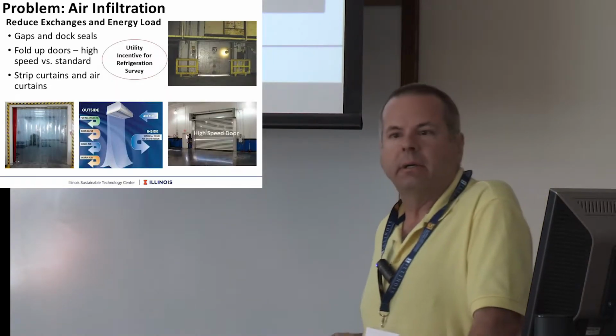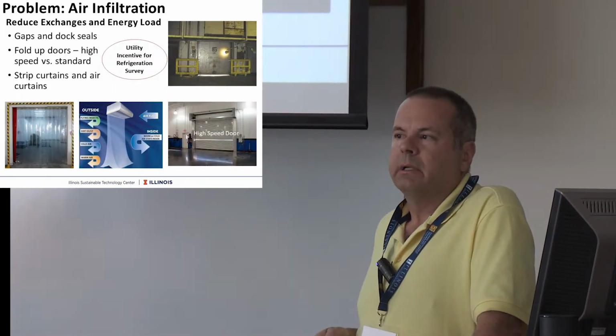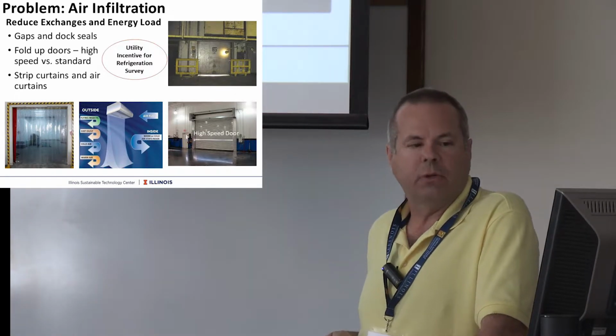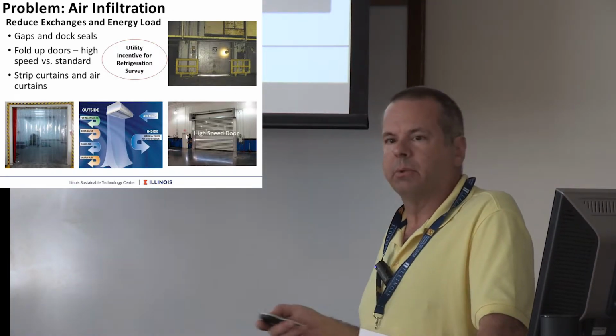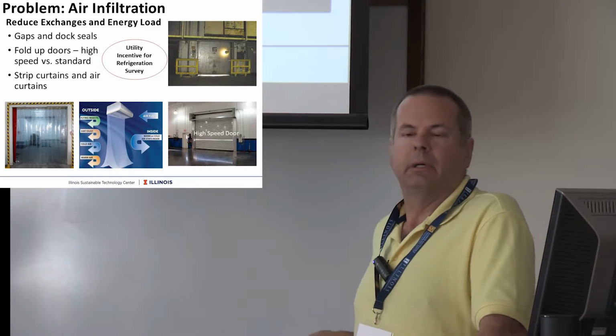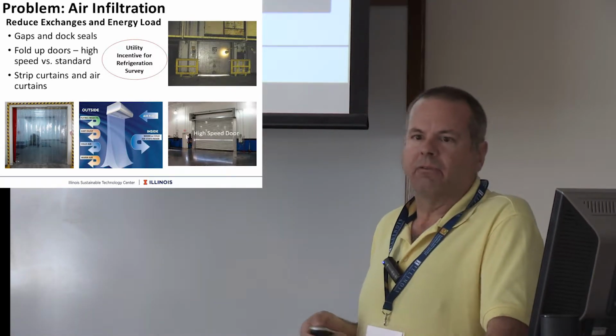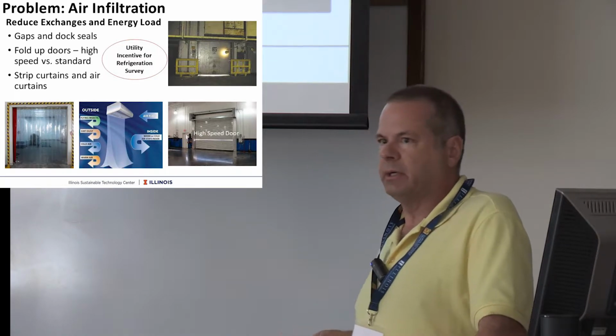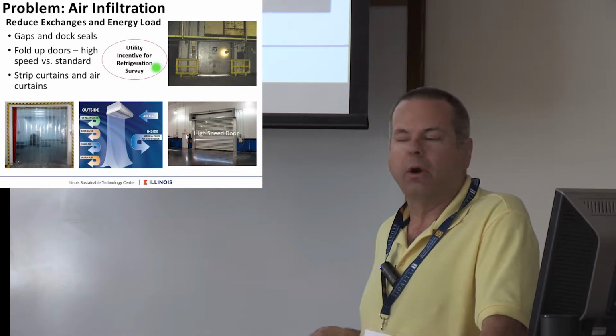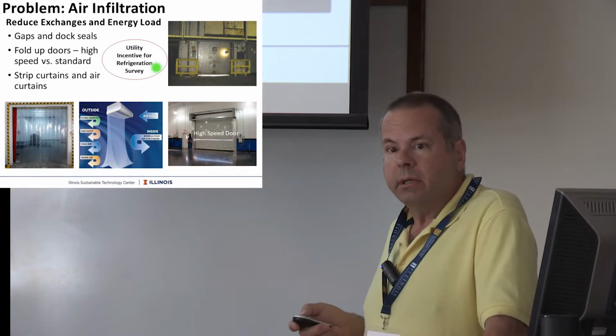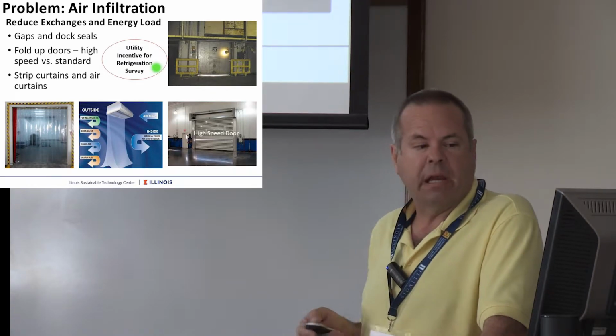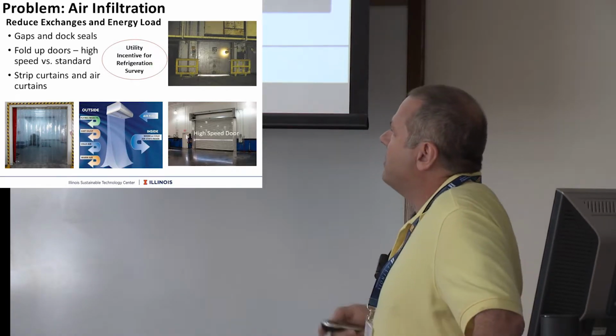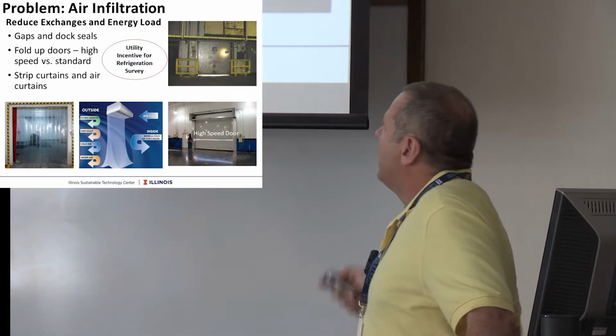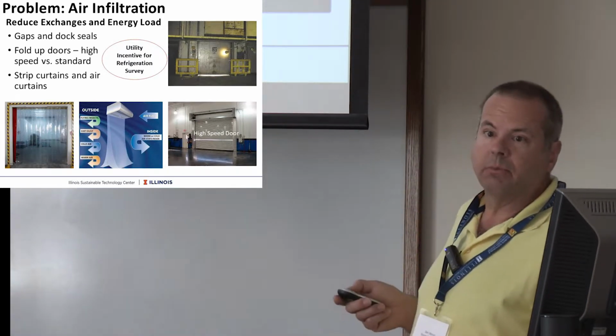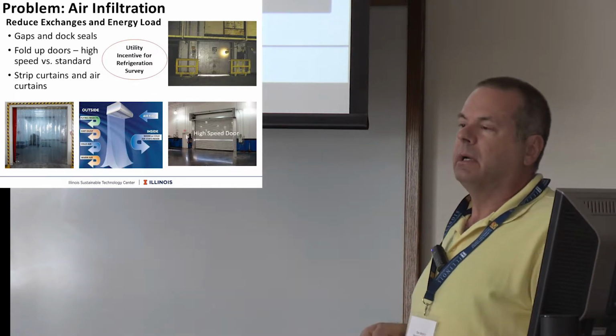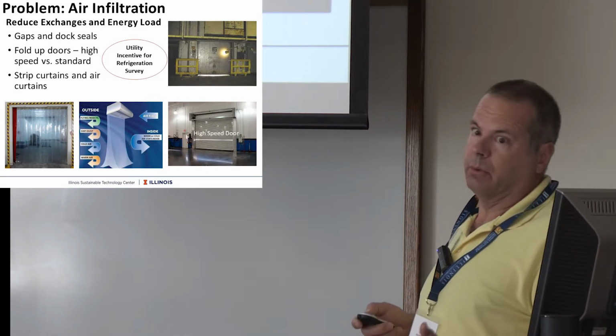Refrigeration, it's all about controlling air infiltration. It has to do with the size of your opening, the temperature differential between the rooms, pressure differential, whether it's negative or positive, but controlling air infiltration is a significant opportunity. There are incentives for refrigeration studies. And I'm just throwing out some things here. You probably have these in your facilities: air curtains, strip curtains, high-speed roll-up doors instead of standard roll-up doors, so that you're minimizing that air exchange that you don't want to have.